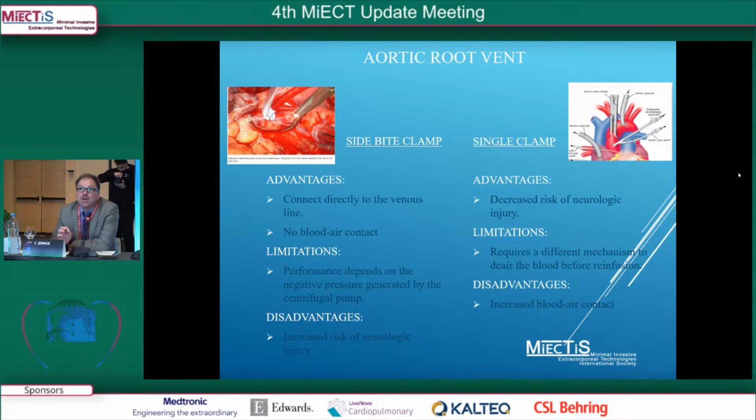It does require a different mechanism to de-air the blood before reinfusion, especially during the proximal anastomosis. Distals, there shouldn't be much air-blood contact, but once that aorta is open and you're actively sucking on the vent, you're going to get a lot of air back. So you have to deal with that some way. And again, the big disadvantage is increased blood-air contact.